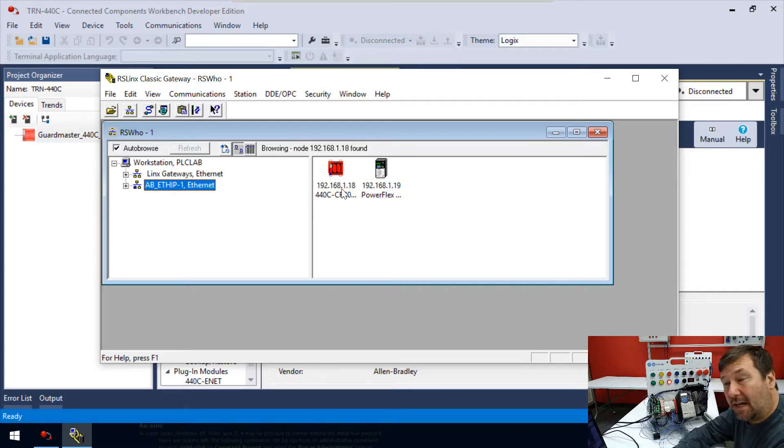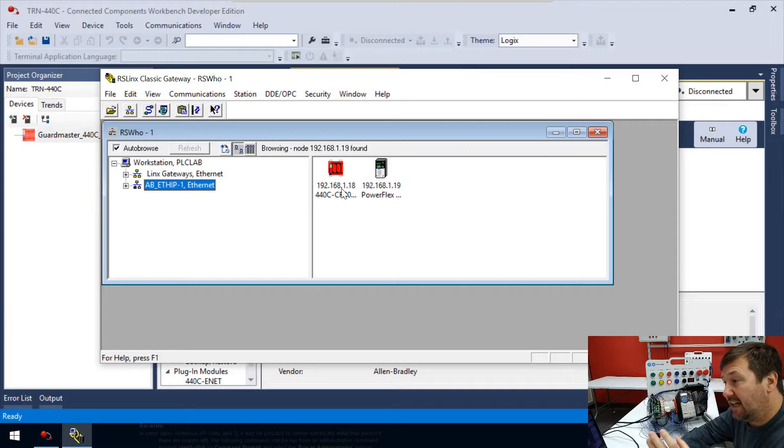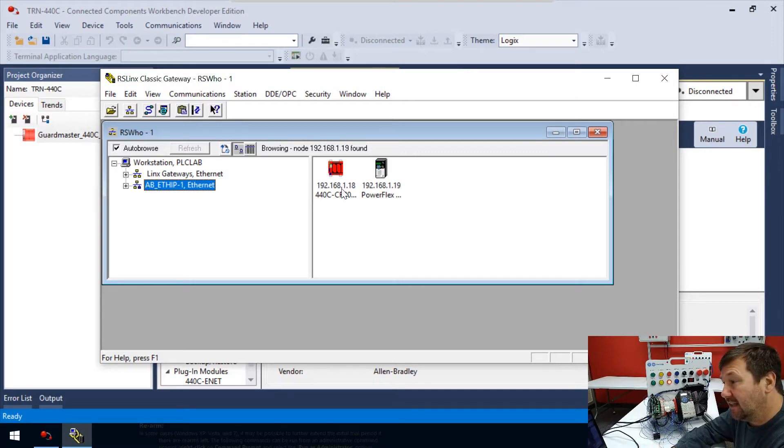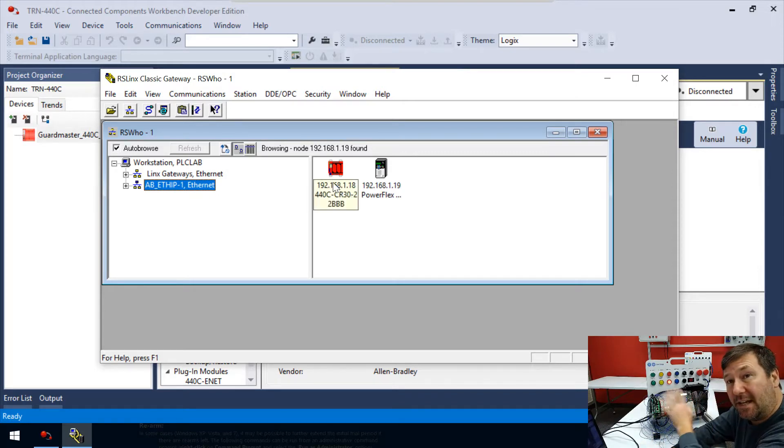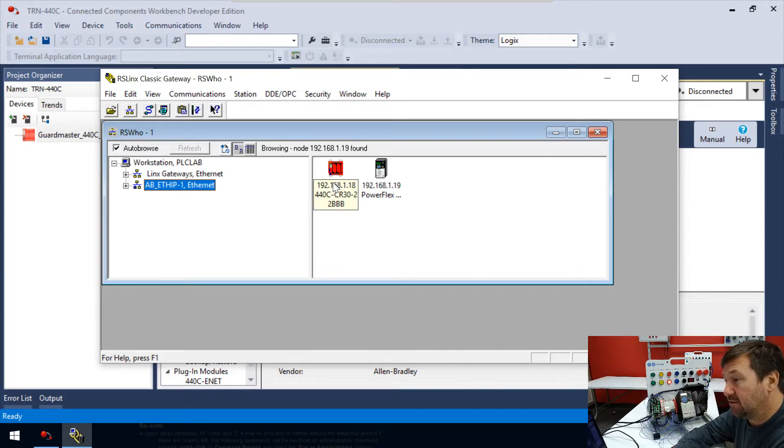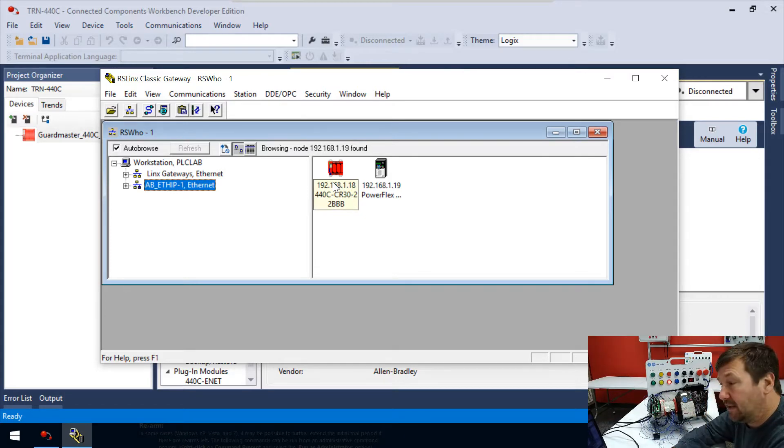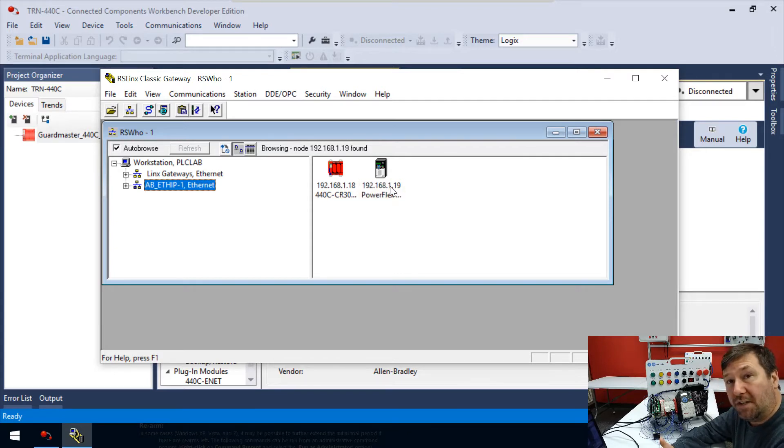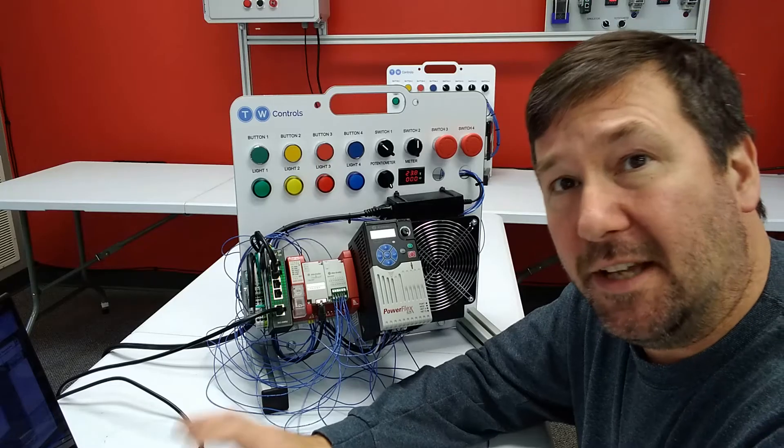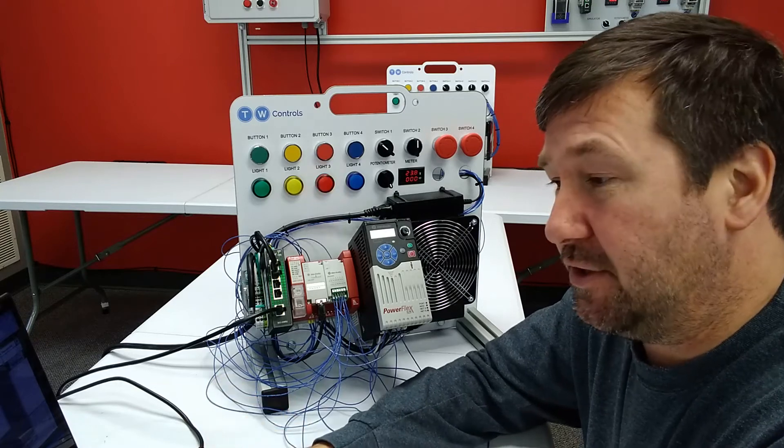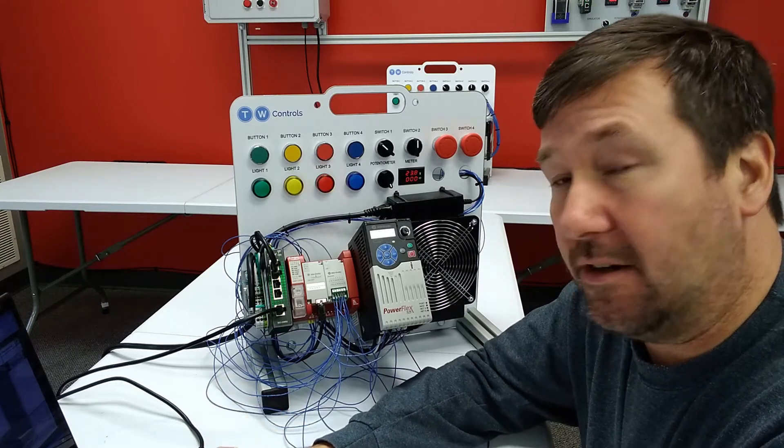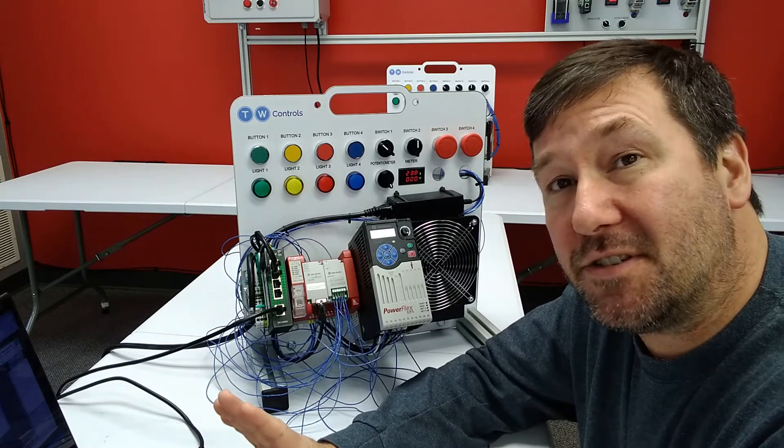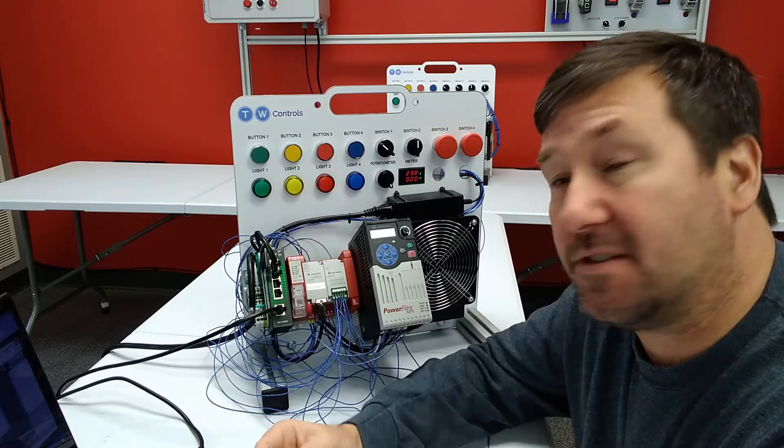We're going to click on the new AB-ETH-IP-1, and immediately we get our two devices. We have our red device here, which is the 440C-CR30, and we have our PowerFlex drive. In your case, if you're using our trainer, the default IP address is 192.168.1.10. Mine is on 18 because we have this set up for some other videos. Your drive is going to be 192.168.1.12. That's the only difference you should see here.